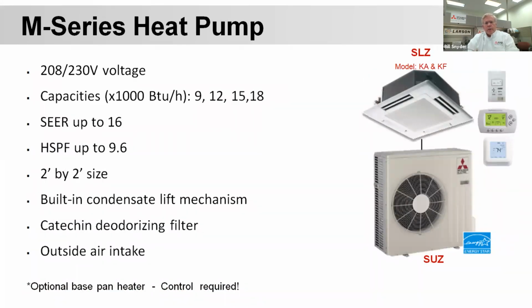Okay, now this particular heat pump is an SUZ outdoor unit. Notice it starts with the letter S. Because it starts with the letter S, we have to put some sort of controls on it. This unit does not have any infrared sensor on it, so you will not have the infrared remote. In this case, that is a simple MA control, which is a 2-wire, just 2 18-gauge thermostat wires, that go up to this particular head, which can mount in a drop ceiling.